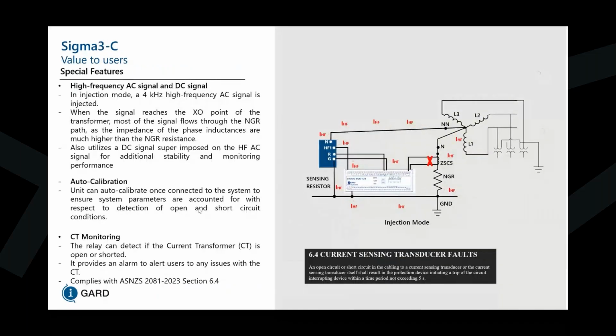Now, the special features that are coming into play is that we are using a high frequency AC signal and a DC signal. So in injection mode, a 4 kilohertz high frequency AC signal is injected. And when the signal reaches the XO point of the transformer, most of the signal flows through the NGR path, as discussed, to properly monitor this entire path. And we also utilize a DC signal superimposed on the high frequency AC signal for additional stability and monitoring performance, especially for instances where there's a lot of capacitance in the system.